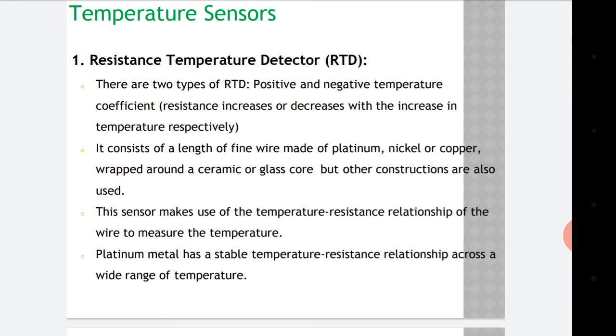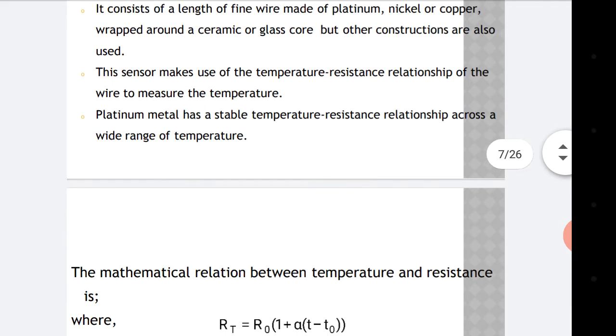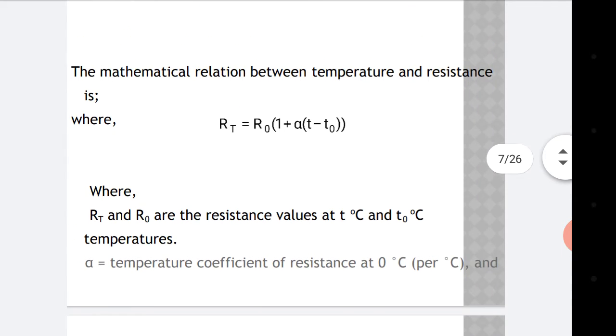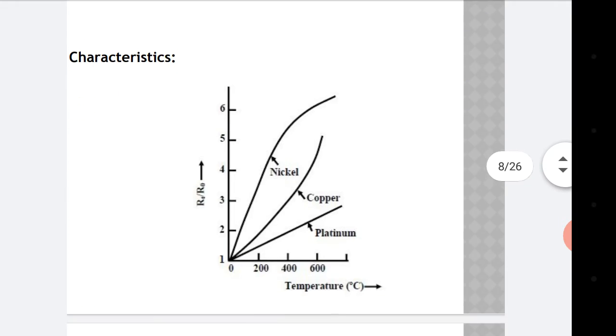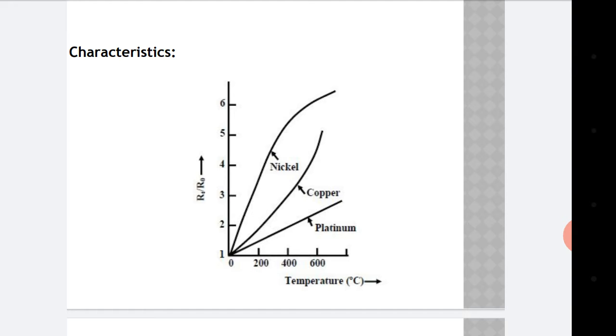Platinum metal has a stable temperature-resistance relationship across a wide range of temperatures. The mathematical relation between temperature and resistance is: R_T = R_0 × (1 + α(T − T_0)), where R_T and R_0 are the resistance values at T degrees Celsius and T_0 degrees Celsius respectively, and α is the temperature coefficient of resistance at zero degrees Celsius.